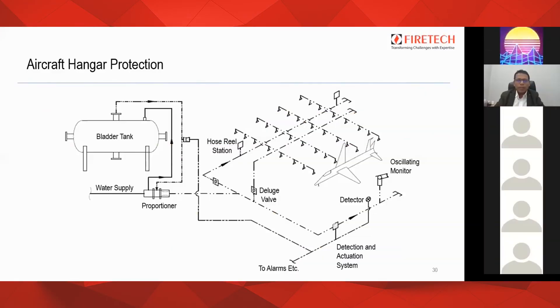A typical arrangement of how a foam system is provided for aircraft hangar protection. Whether there is a requirement of a foam system for an aircraft hangar or not depends on what is the type of hangar and what is the group of hangar as per NFPA 409.